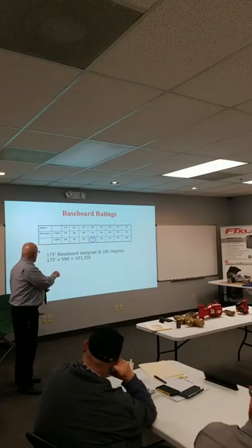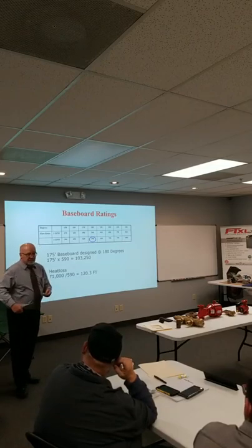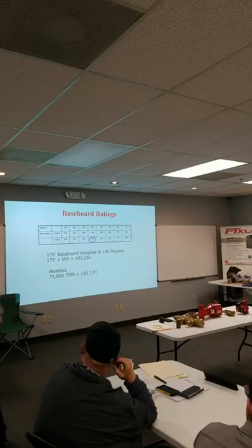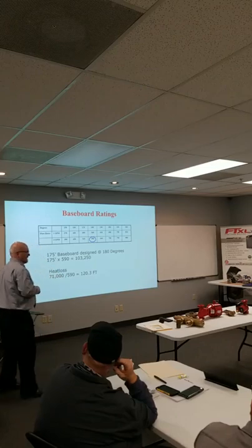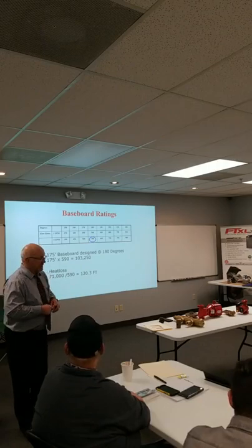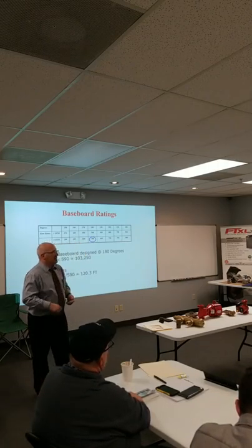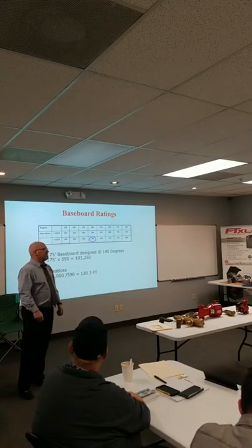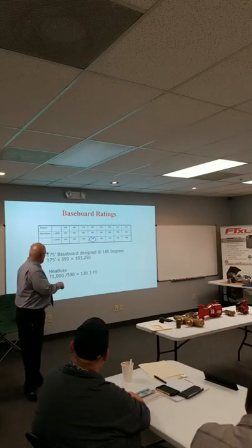So we got this equation. Now we do a heat loss. We find out that the heat loss of that house is 71,000 BTUs. And did you know that this side of the Mississippi, the average residential heat loss is about 70 to 75,000 BTUs? That's all it is. Average. What's the average size house? 2,000 square foot? 1,500 square foot? Probably between 1,500 and 2,200. Yeah. And most of it is that.